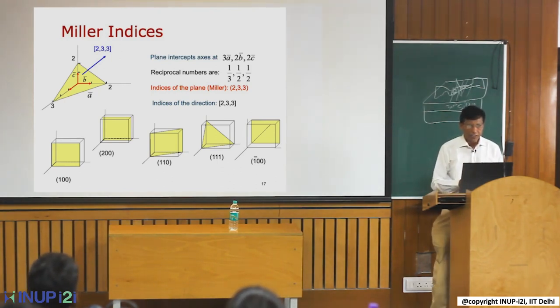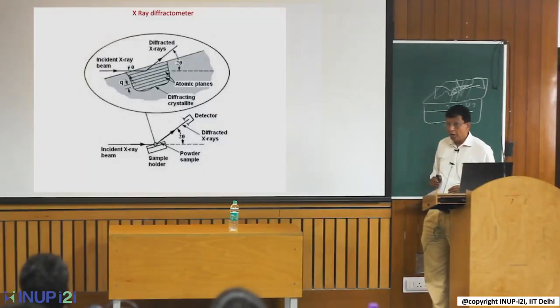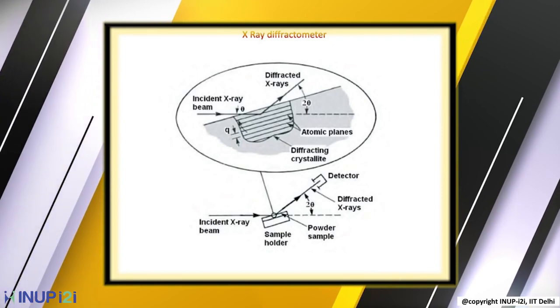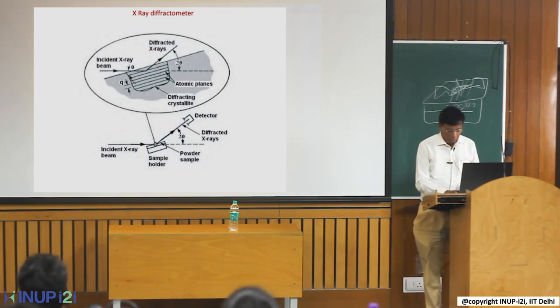In an X-ray diffractometer, you have an X-ray source, a specimen, and a detector. The sample is kept on a stage. For bulk powder samples or thin film samples, there are different mounting methods. The technique is based on Bragg's Law, where X-rays incident on crystal planes are reflected and interfere to form peaks. Here lambda is the wavelength, theta is the incident angle, and d is the spacing between planes.